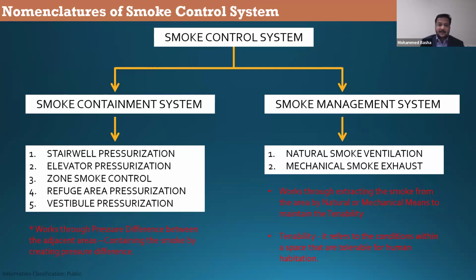So these are the fundamentals of smoke control systems: what is smoke containment and what is a smoke management system? Because we use a single term, smoke control system, it has different names and different systems to be used. In the smoke management system, we have another system called the smoke clearance system, which I have not referred to here. The smoke clearance system is also called the smoke purging system. It is used after a fire event to remove the byproducts of fire, which are carbon monoxide or smoke, after the fire has been extinguished.